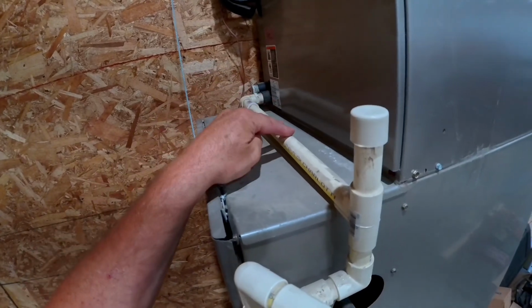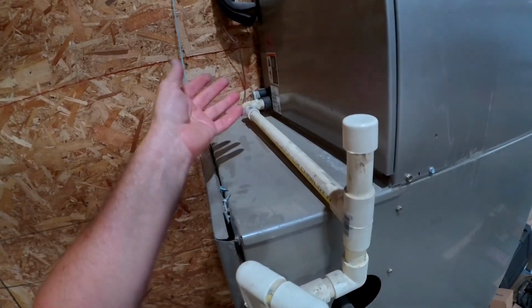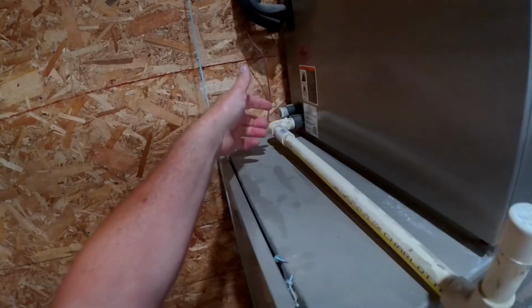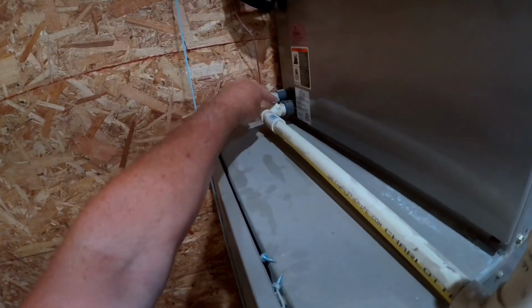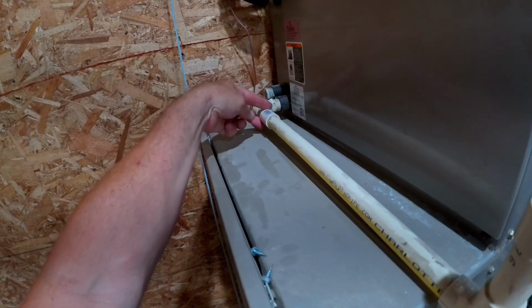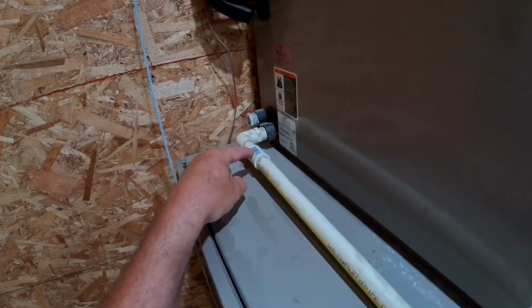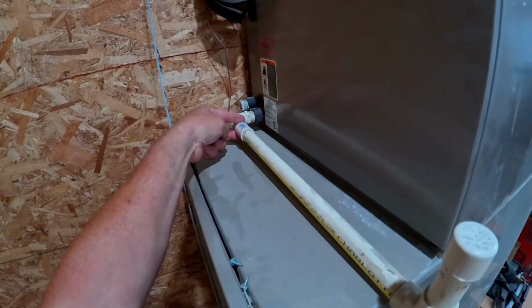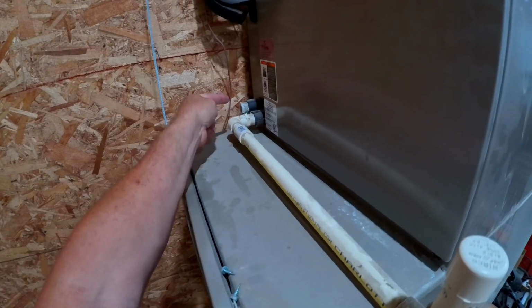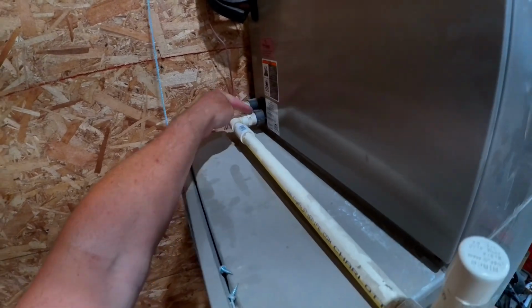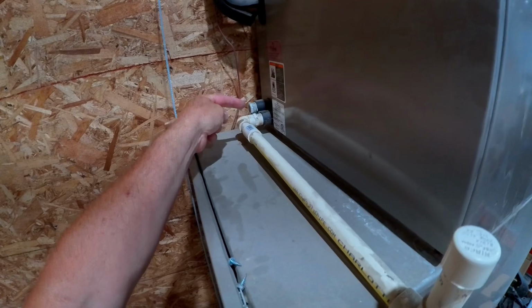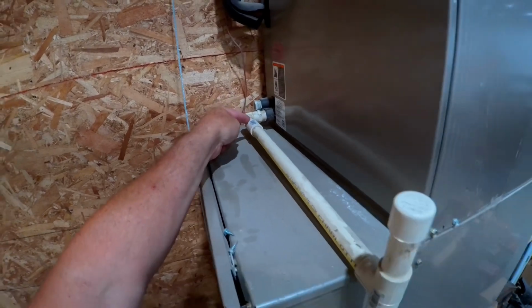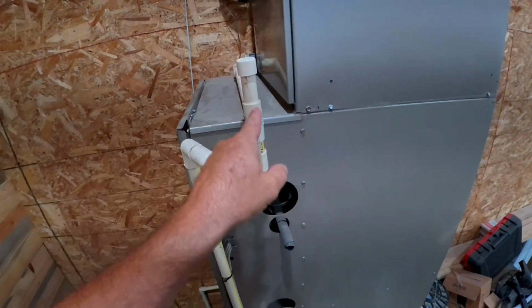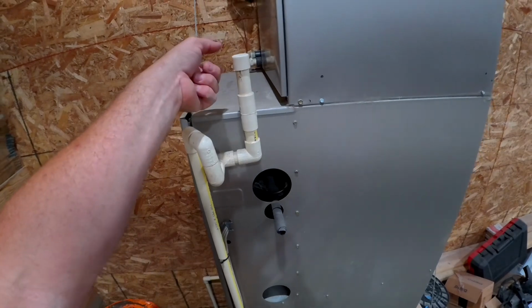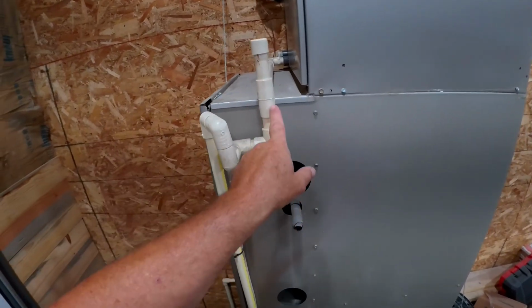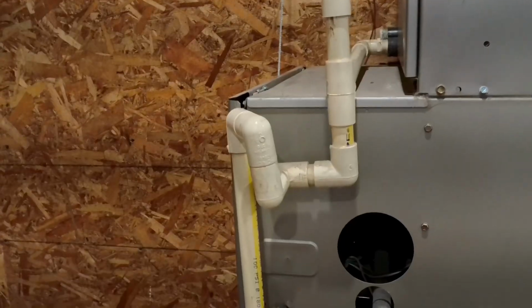Now this is just standard pipe that we can get from any big box store, so the repair is fairly simple. We're going to go through and cut it somewhere close to this elbow right here. So when we cut this line, which you can always see a coupling here, it's going to allow us to unscrew this fitting out of here and check this system to make sure it's clear. After that's also cut there, that's going to allow us to remove the condensate system and blow air or water down through it and clean out the P-trap area.